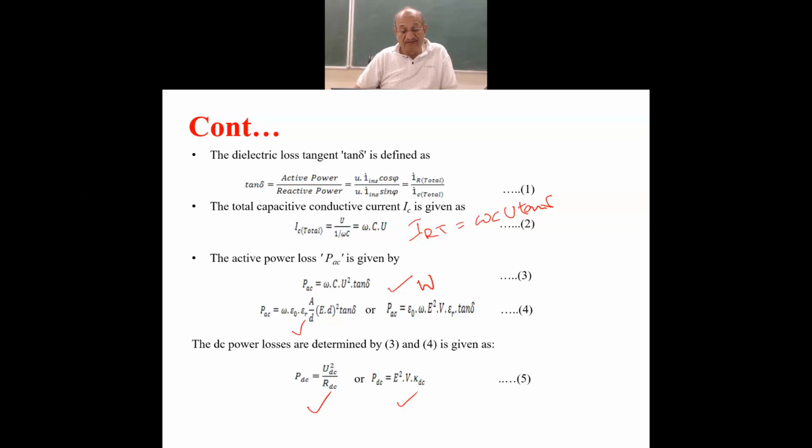What we have seen here is that the knowledge of tan delta, known as the dielectric loss factor also, is important. Of course, it's not constant. It is a function of the magnitude of the voltage applied, and it is a function of the frequency of the voltage applied.